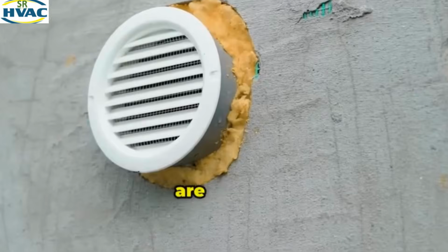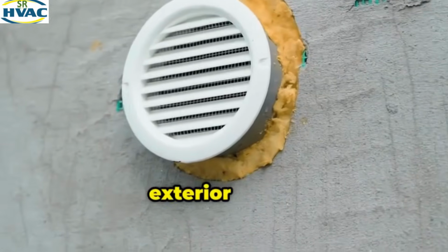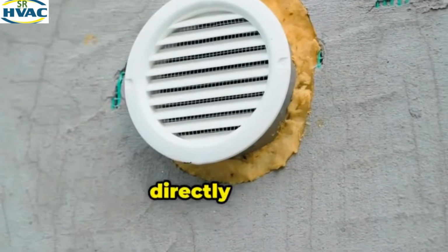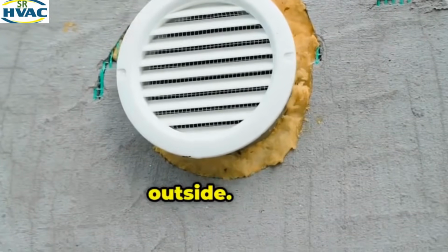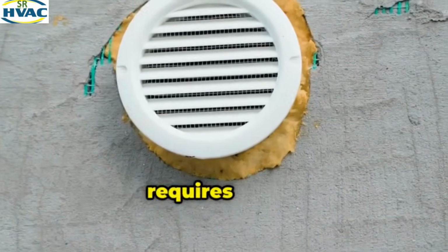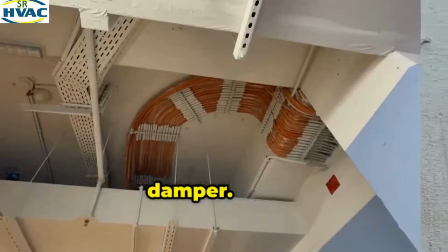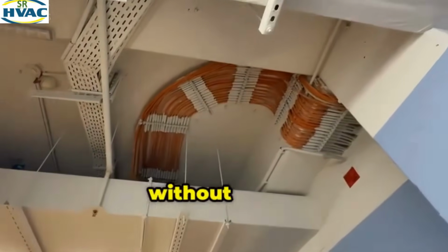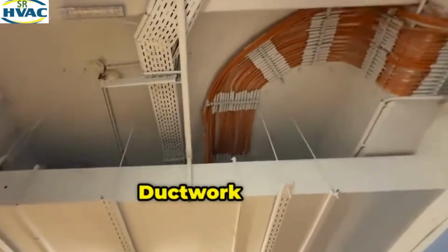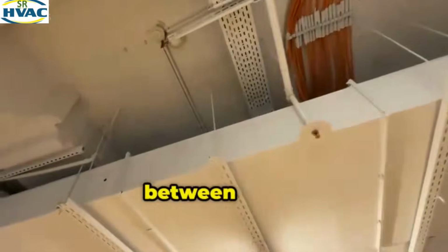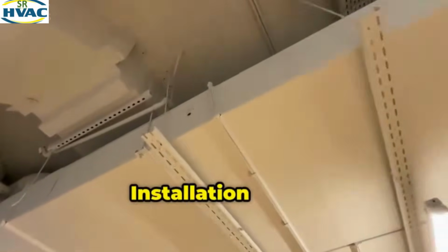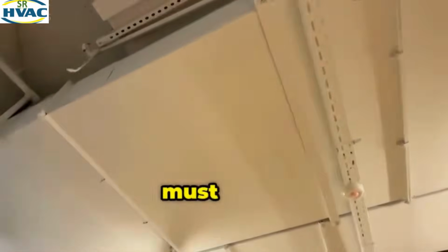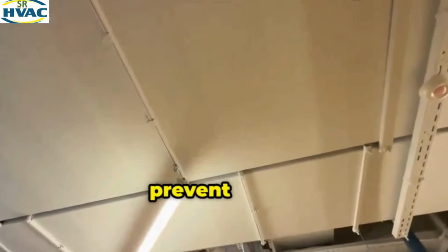Wall mounted fans are a common solution for rooms with an exterior wall. They install directly through it, pulling air straight outside. Installation is straightforward but requires a proper seal and a backdraft damper. Ceiling mounted fans are popular for rooms without an exterior wall. Ductwork runs through an attic or between joists to the outside. Installation is more complex and you must insulate the duct to prevent condensation.